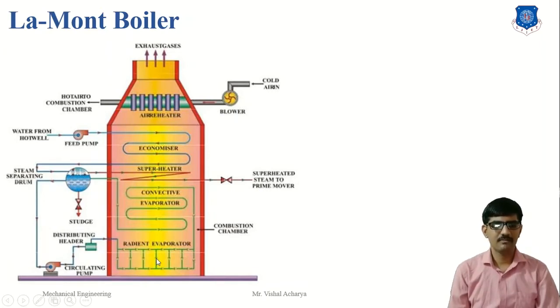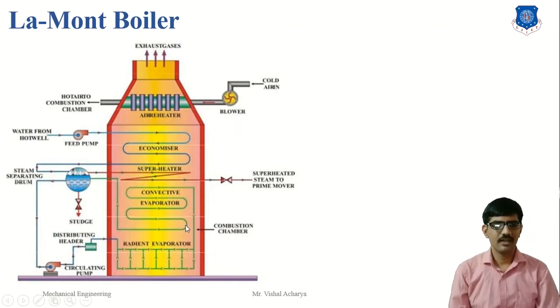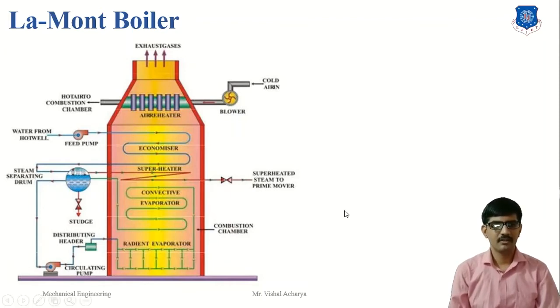In the radiant evaporator, the temperature of water is increased by radiation, producing a water and steam mixture, which is then transferred to the convective evaporator. In the convective evaporator, almost all the water particles are converted into saturated steam, which is transferred back to the steam separating drum. Steam is separated in the upper part of the drum and transferred to the superheater, where steam temperature increases and is converted into superheated steam, which is then supplied to the turbine blades.